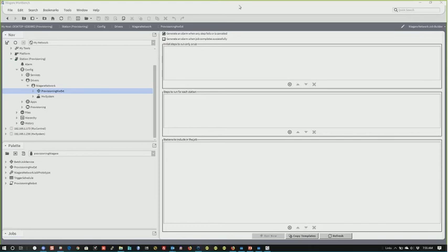Hey, Frank, Doug and I were discussing something on the passphrase last week. We downloaded your videos, and could you go over a little bit how you could bypass the passphrases now, and does that somehow let you get a station out of an N4 JACE if you don't have credentials? There is no bypassing a passphrase on a JACE unless you blow the JACE away. You can reset the passphrase of a station that you already have. If you get a station from someone and it has the passphrase, you can blow the passphrase out. The problem is when you do that, you get rid of all the passwords on all of the users that were encrypted using that passphrase. Will it only remove the passwords and nothing else? Correct.